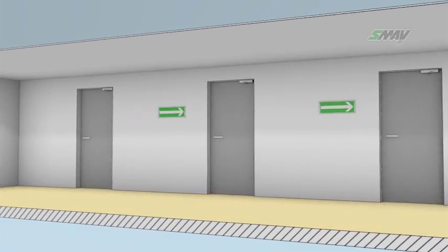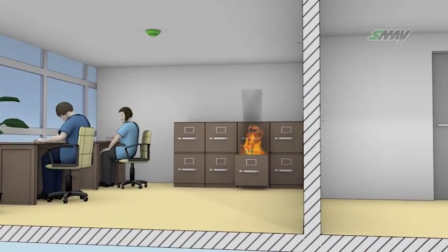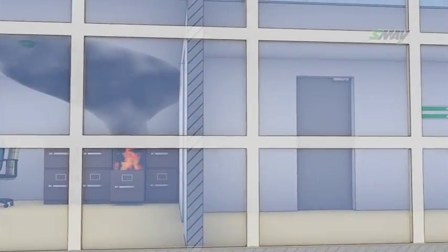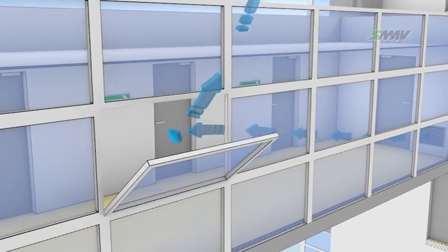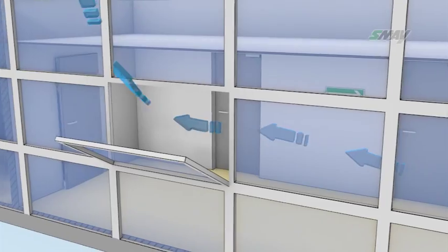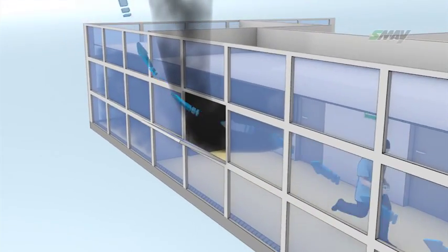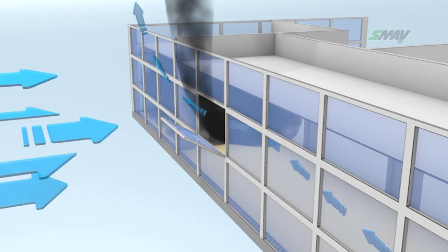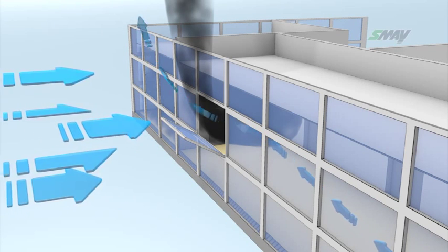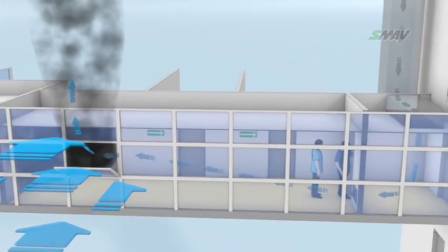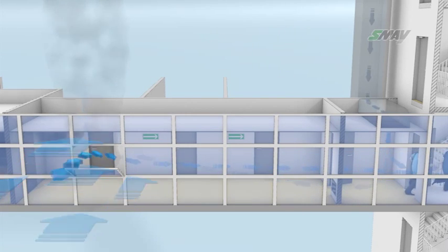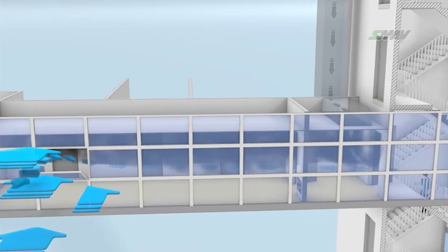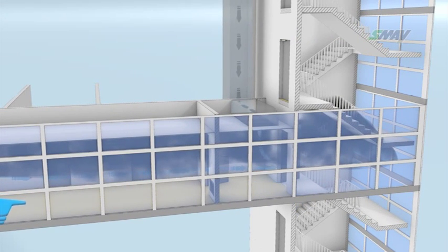Designing appropriate air release in the corridor will ensure that the smoke will be extracted from the corridor. Air may be extracted by mechanical smoke extraction installation or natural, for example a window, ventilation may be used. The detrimental effects of external factors should be taken into consideration if using natural ventilation. For example, strong wind blowing at right angles to the facade with the window may cause a zone of overpressure, which will, if the doors between the corridor and the stairwell are opened, prevent effective extraction of the air and smoke mixture. As the air and smoke is not being extracted, it may flow into the stairwell.